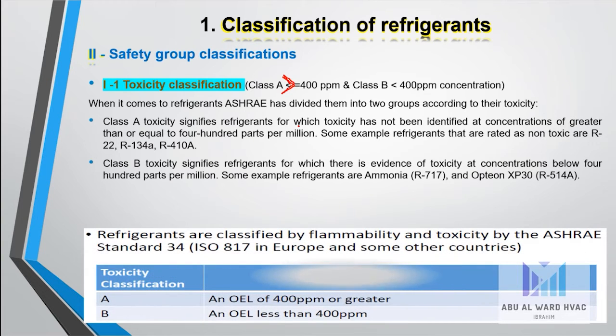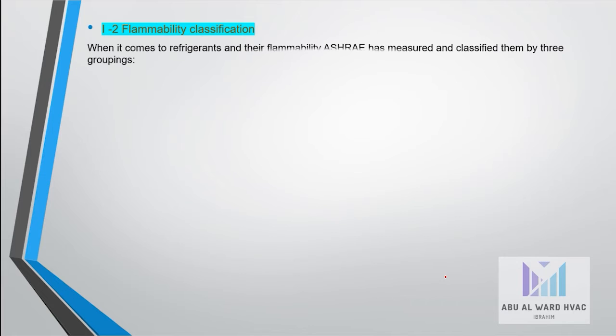According to ASHRAE, refrigerants are classified by toxicity: class A for concentrations greater than or equal to 400 ppm, and class B for concentrations less than 400 ppm.